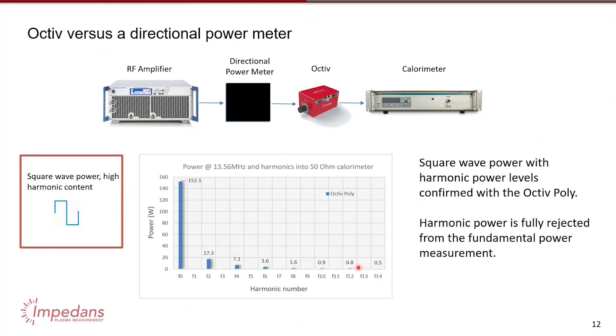The calorimeter was measuring 185 watts total. The VI probe was measuring 152 watts in the fundamental frequency, the 13.56, so not the harmonics yet. But the directional coupler, which doesn't try to split out frequencies, only measured 130 watts, so it is completely wrong. Harmonic content damages the data basically.